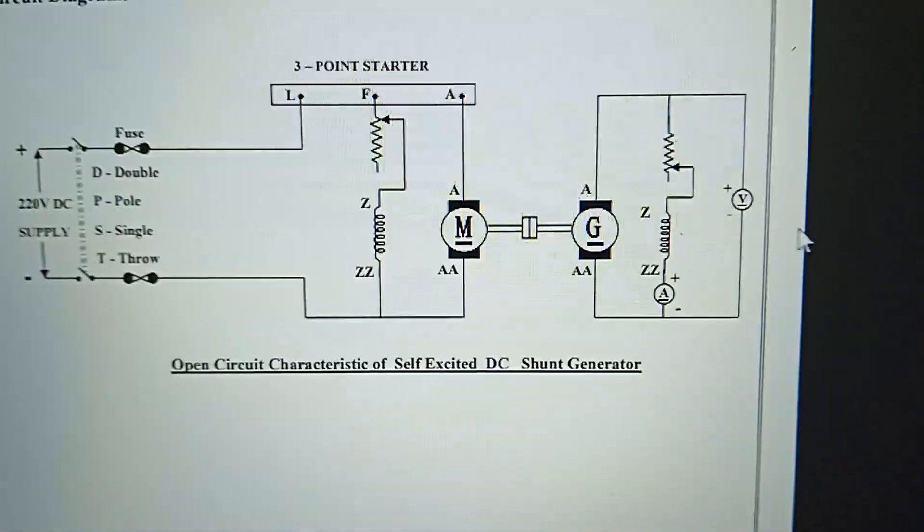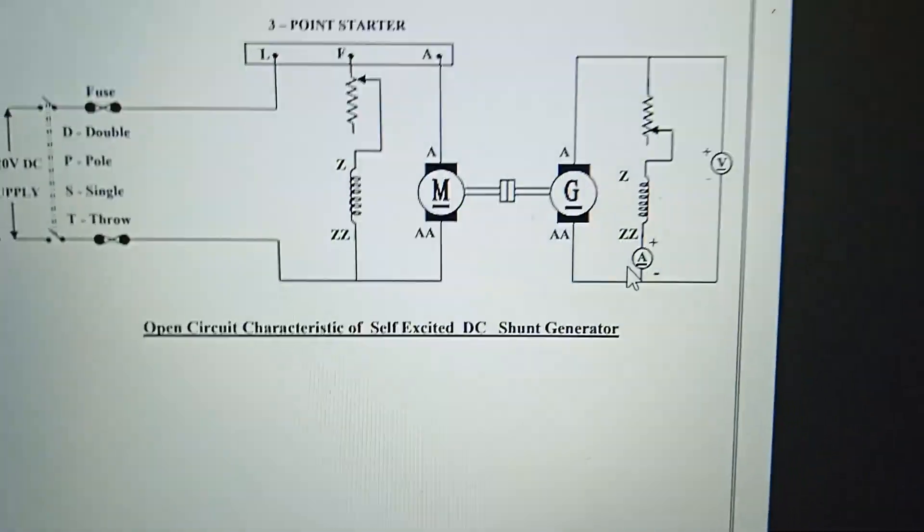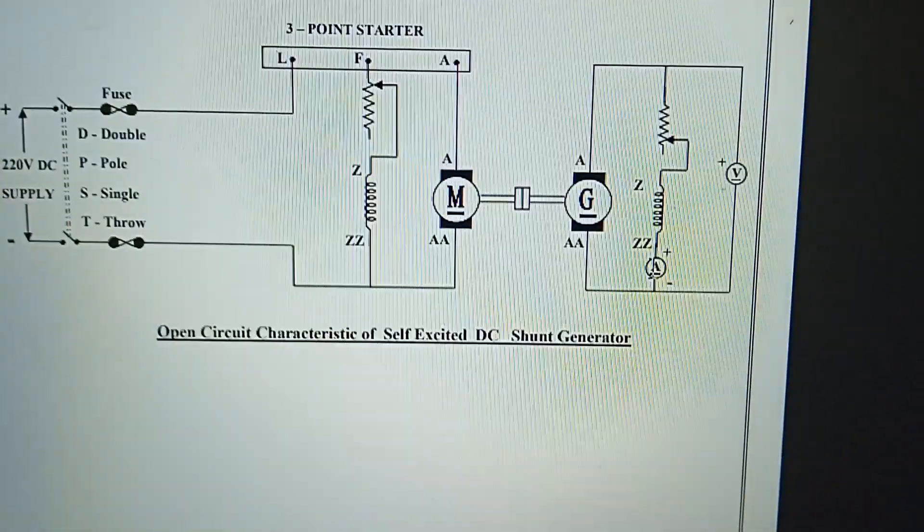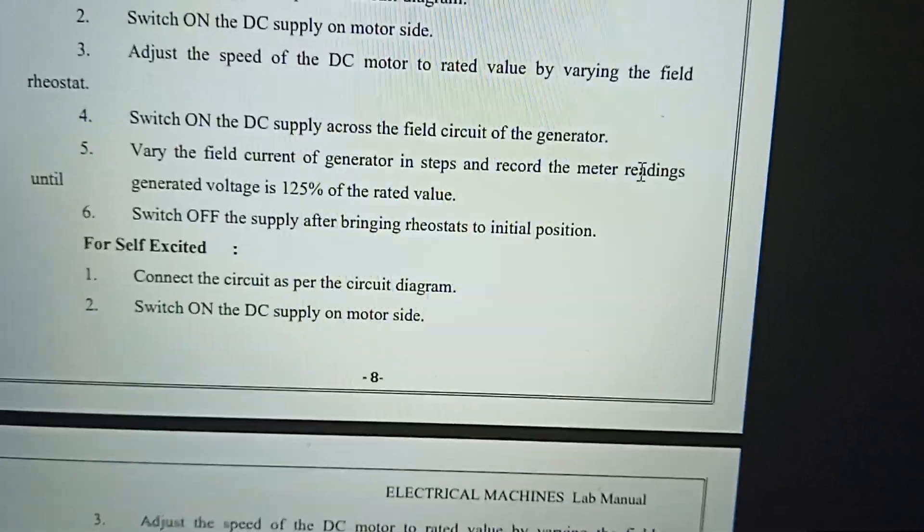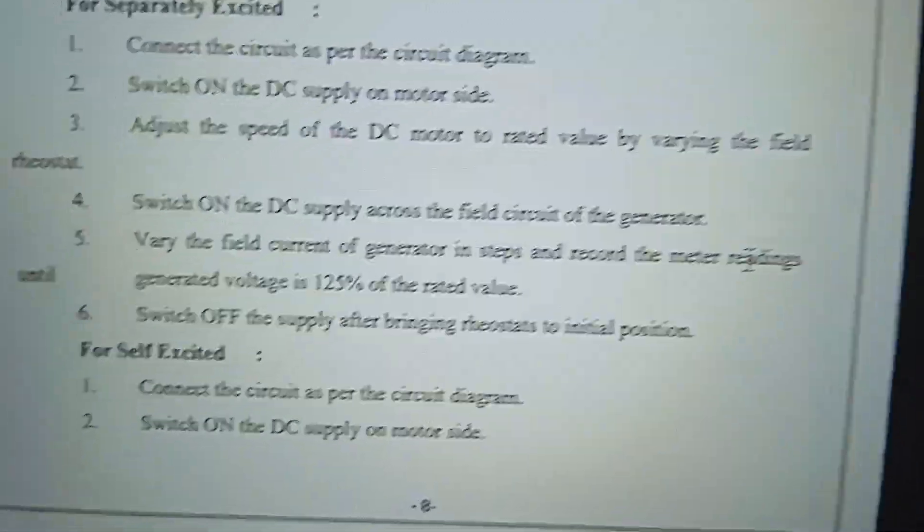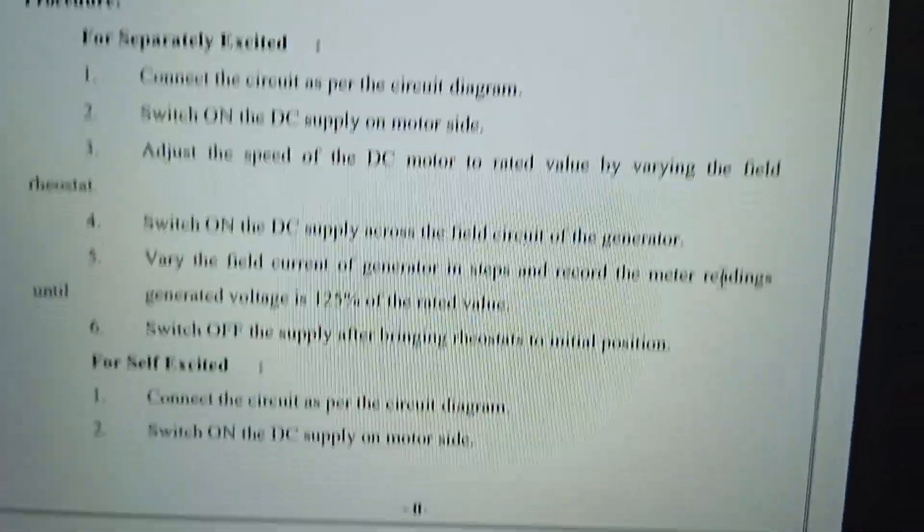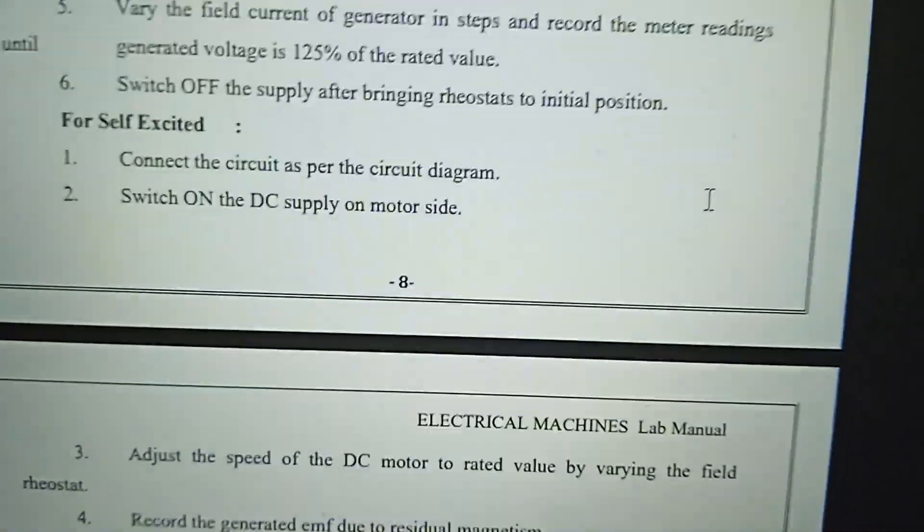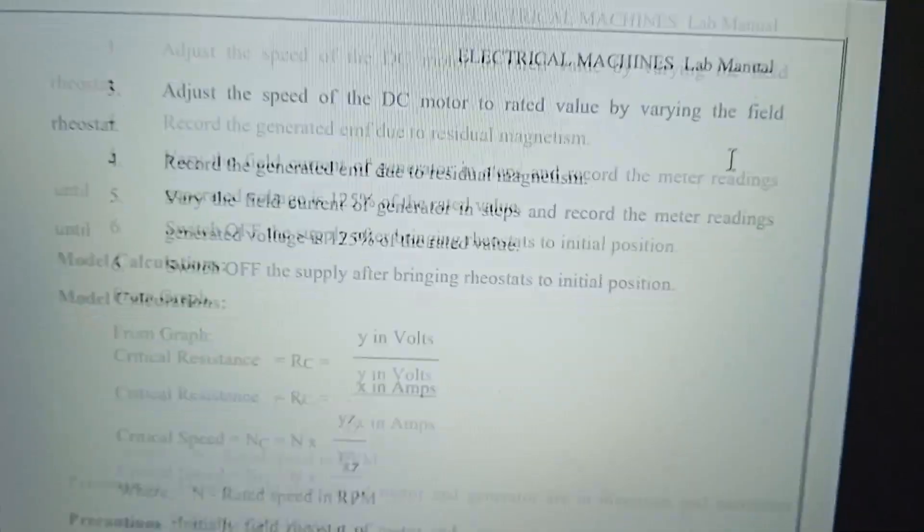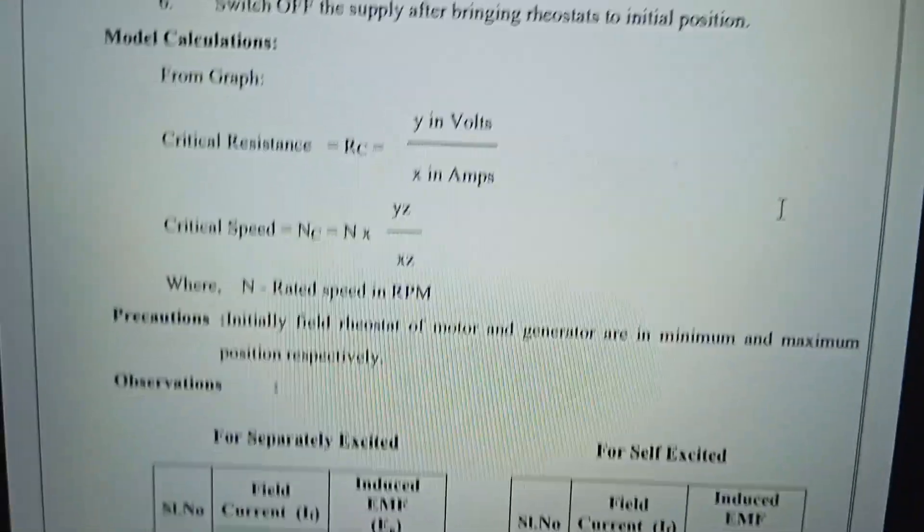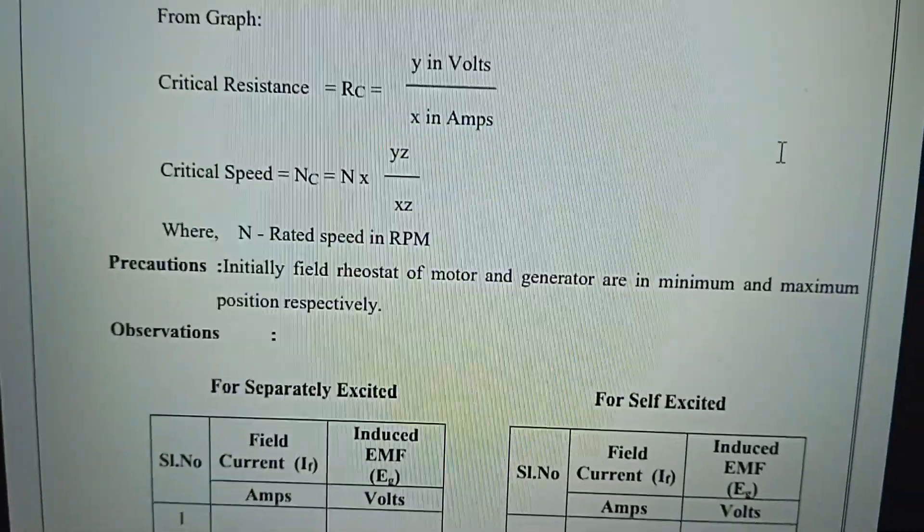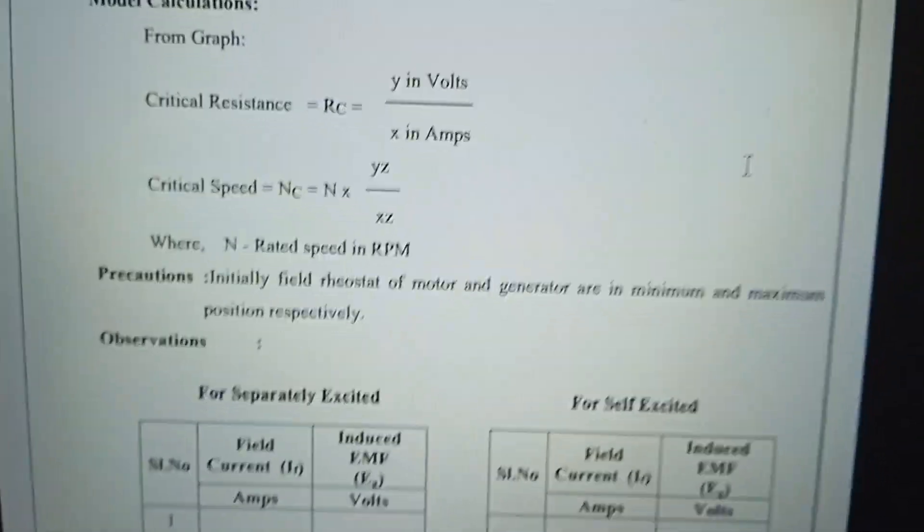Normal voltage values and field current values - 220 volts. We can go up to 125 percent of the rated value, so 1.25 times 220 volts is allowed. Critical resistance RC is Y by X. Critical speed NC is YZ by XZ.